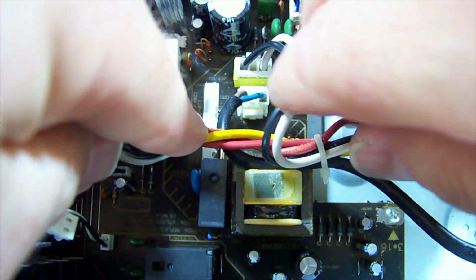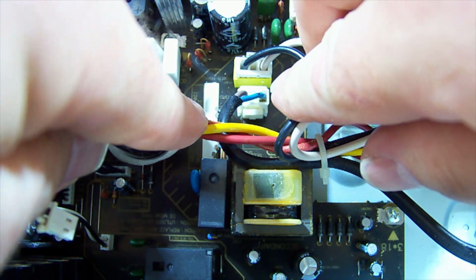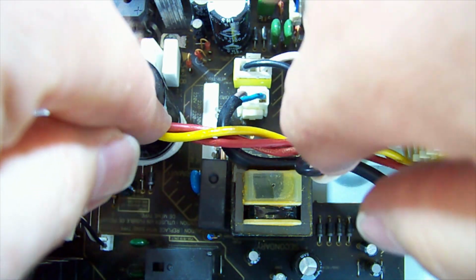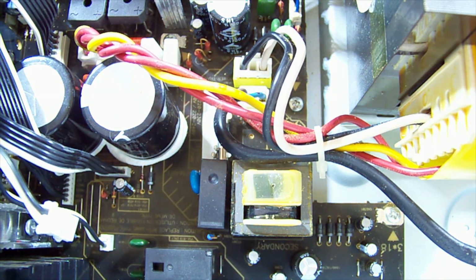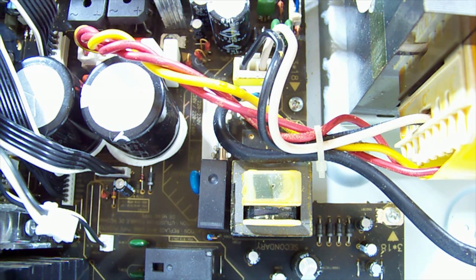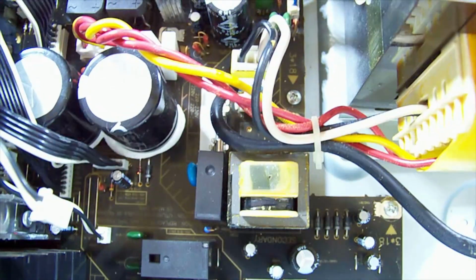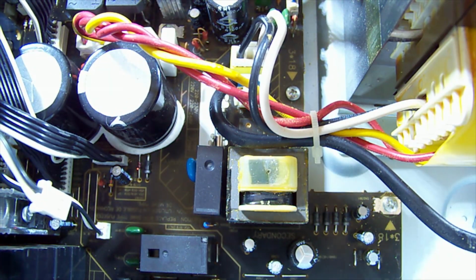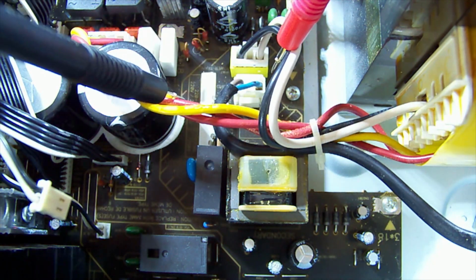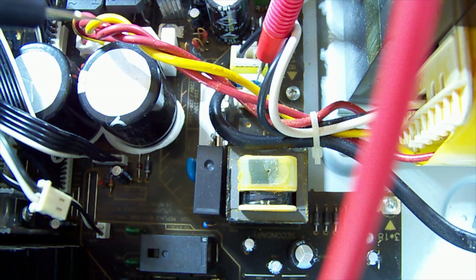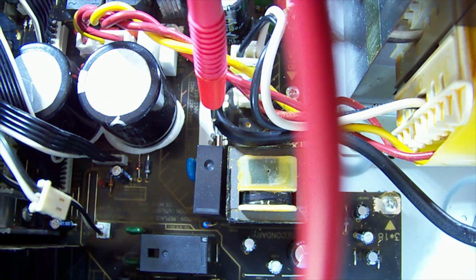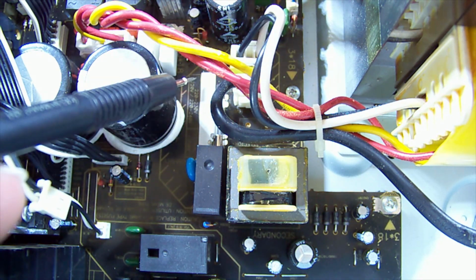So here we have the black wire coming through to the first white connector there with the brown and blue wires. That's our mains input. So let's double check that we have 230 volts there. And we do. Now, hiding down under here, there's our mains input fuse.